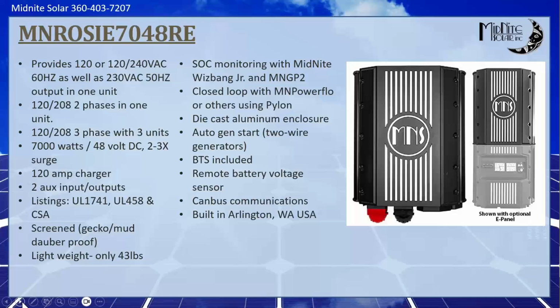Full featured automatic generator start, 2-wire generator start. So you've got your blackout times. You've got several reasons that you can start on: state of charge, voltage, time of day, etc. Then you can stop on multiple reasons: state of charge, voltage, time of day, or going to float. And you can set multiple triggers. So you could tell it, hey, I want you to start at 50% state of charge. And then you can also tell it, hey, I want you to start at 48 volts. So if for some reason the state of charge gets off, the voltage will still kick in. We talked about quiet time, and whatnot, and exercise time is also in there as well.